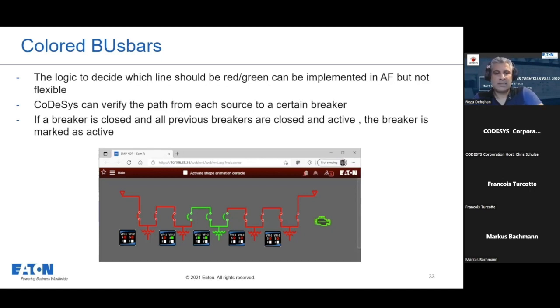With CODESYS, CODESYS can verify the path from each source to a certain breaker. So if a breaker is closed and all previous breakers are closed and active, basically, if there is an active path from a source to a breaker, that breaker is marked as active. And then for each section of the line, if the two breakers on the two sides are active, it means that section is active too.